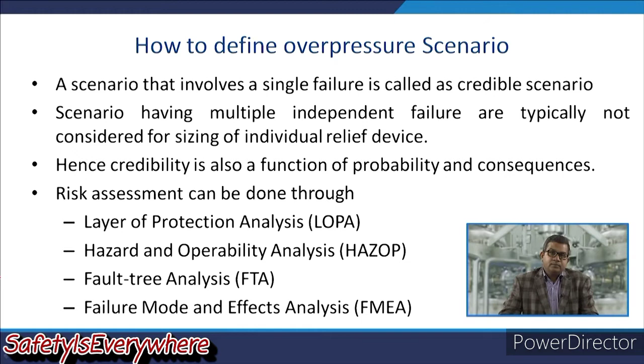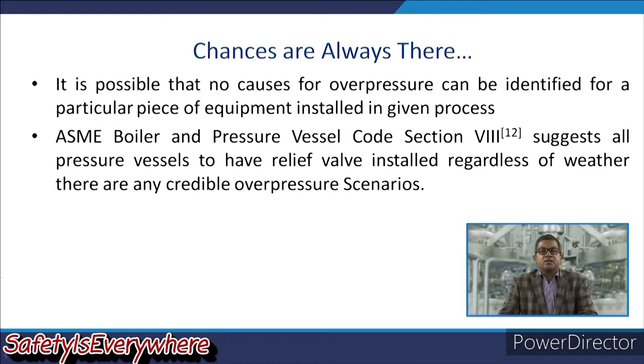Now, it is possible that no cause for overpressure can be identified for a particular piece of equipment installed in a given process. The American Society of Mechanical Engineers, ASME, has developed various codes. The ASME Boiler and Pressure Vessel Code Section 8 suggests that all pressure vessels have a relief valve installed, regardless of whether there are any credible overpressure scenarios or not. So it is mandatory for all boilers, and that's why in the Indian context we have a separate boiler certification code.